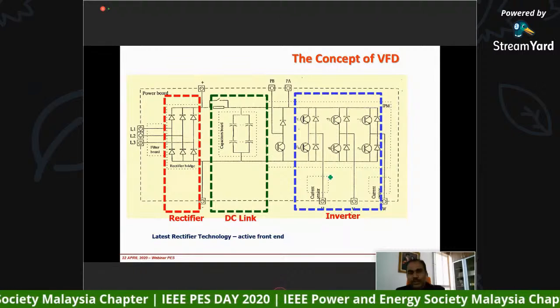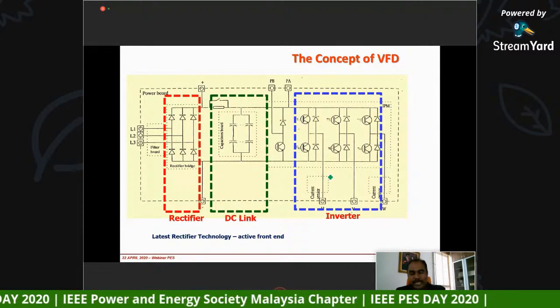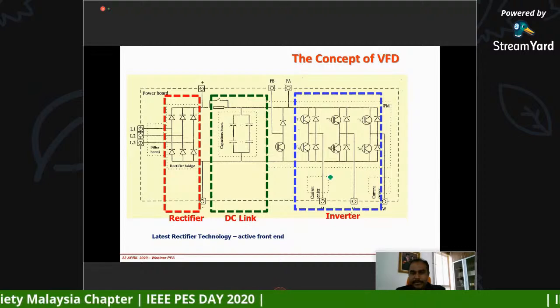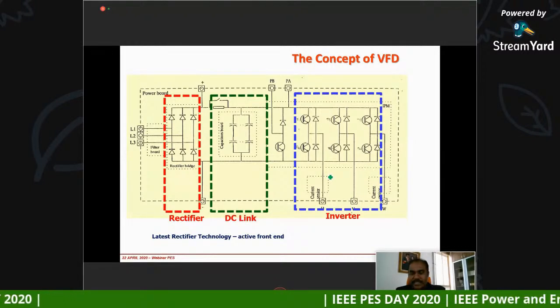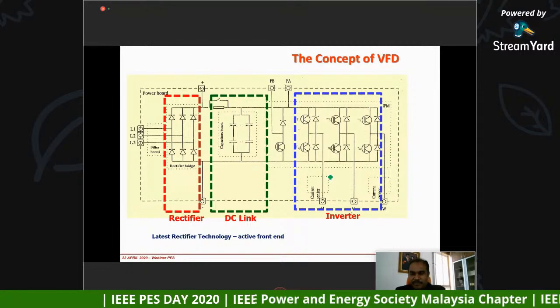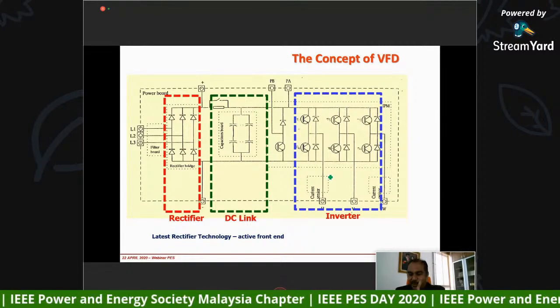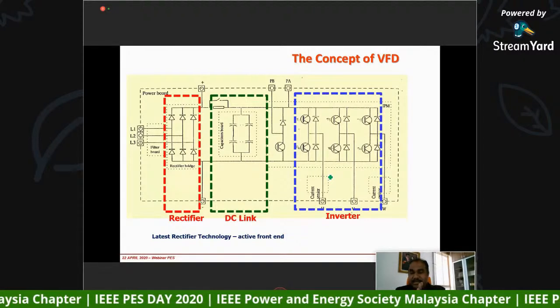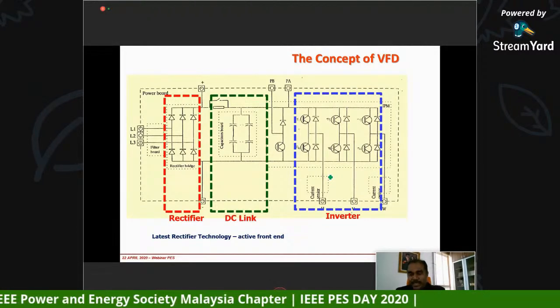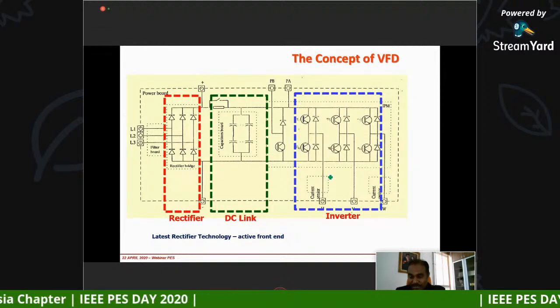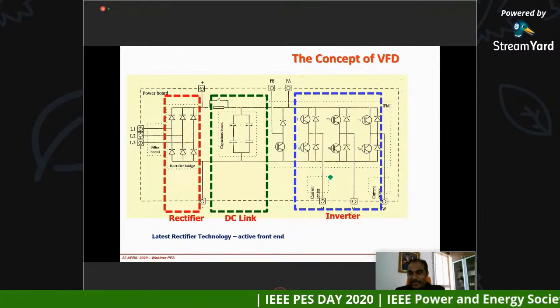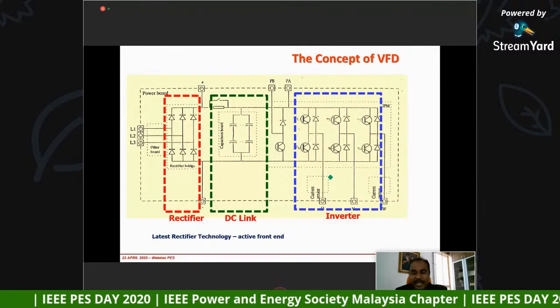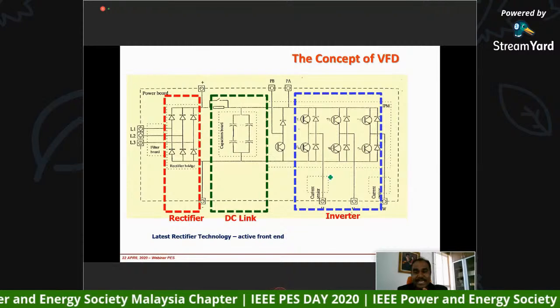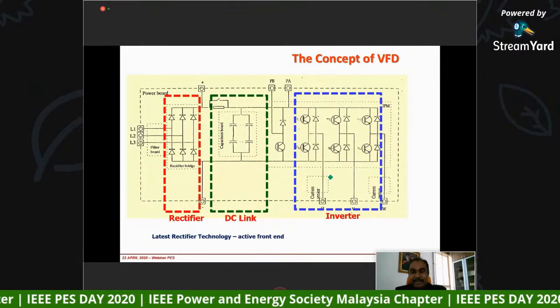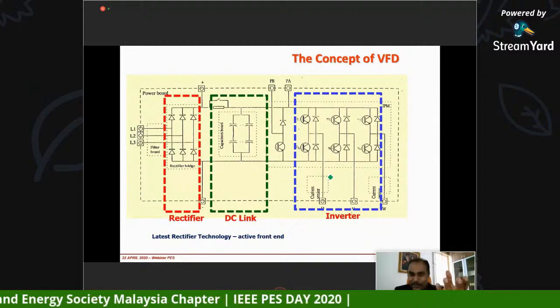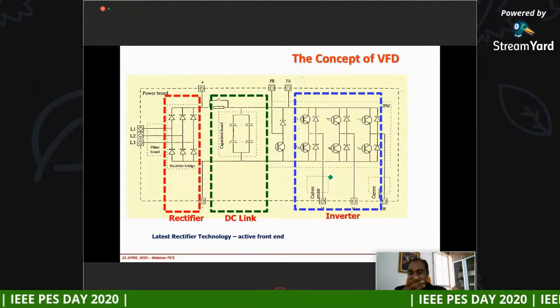So the reason why I show you these slides, I will conclude in the last slides later, is that you have to understand one thing. If you think that a variable speed drive is not going to give you savings, please don't install a variable frequency drive, because there are going to be a lot of maintenance issues, and a lot of maintenance costs will come in when you install one. So you need to be able to justify it.